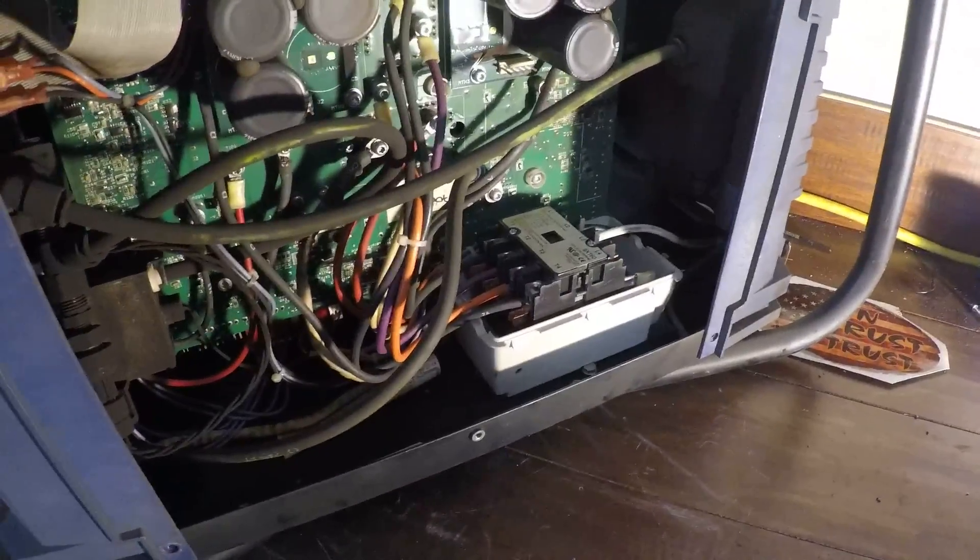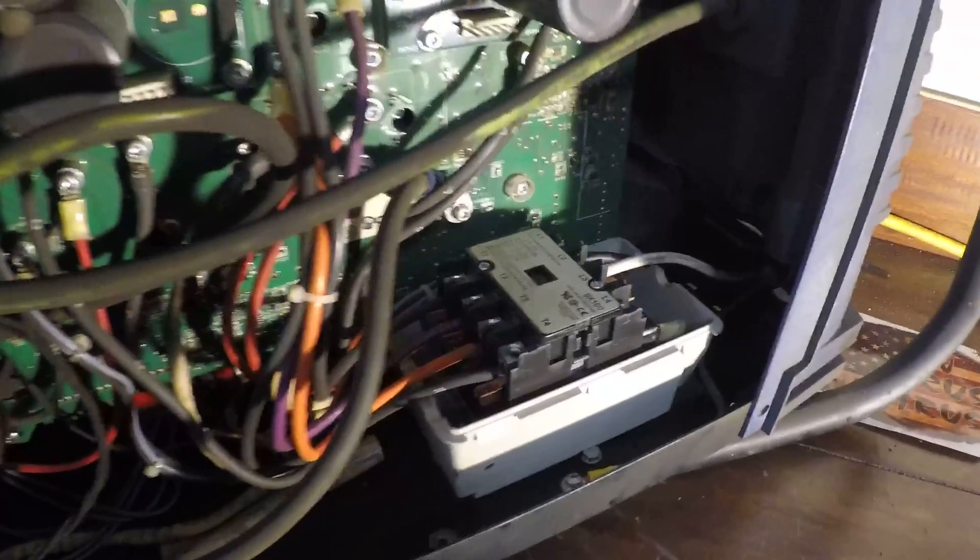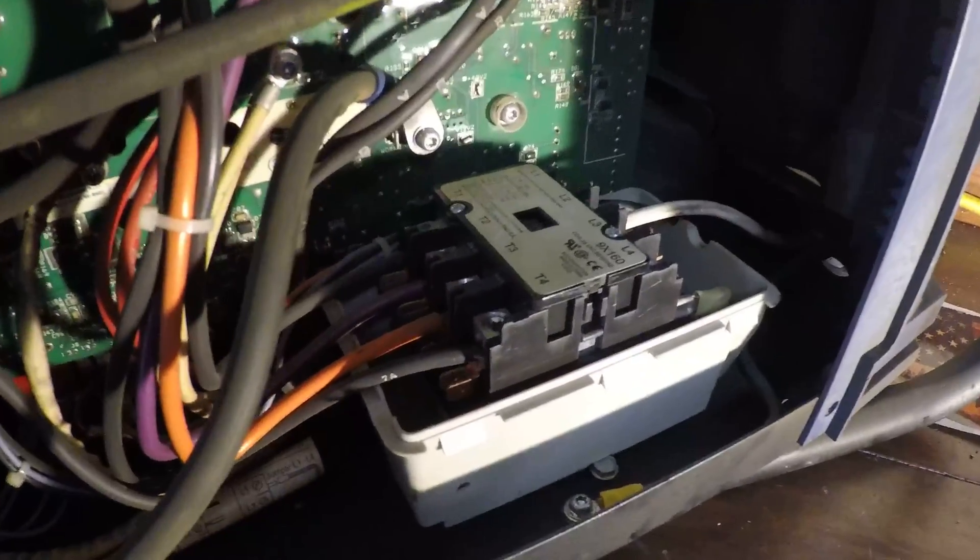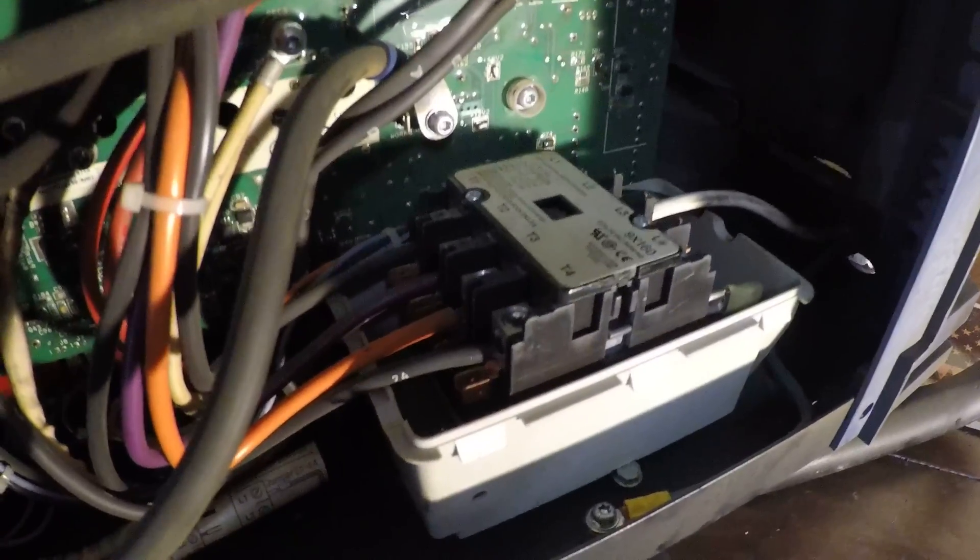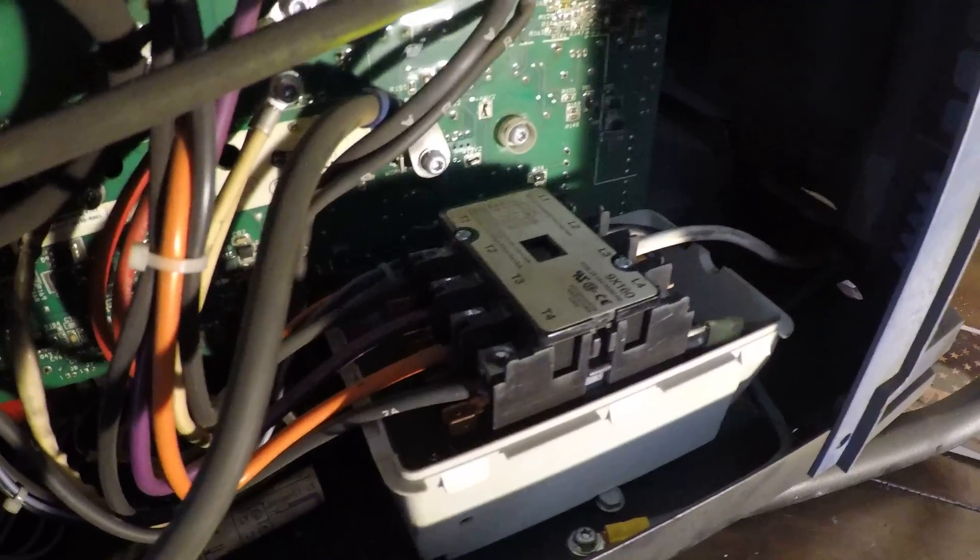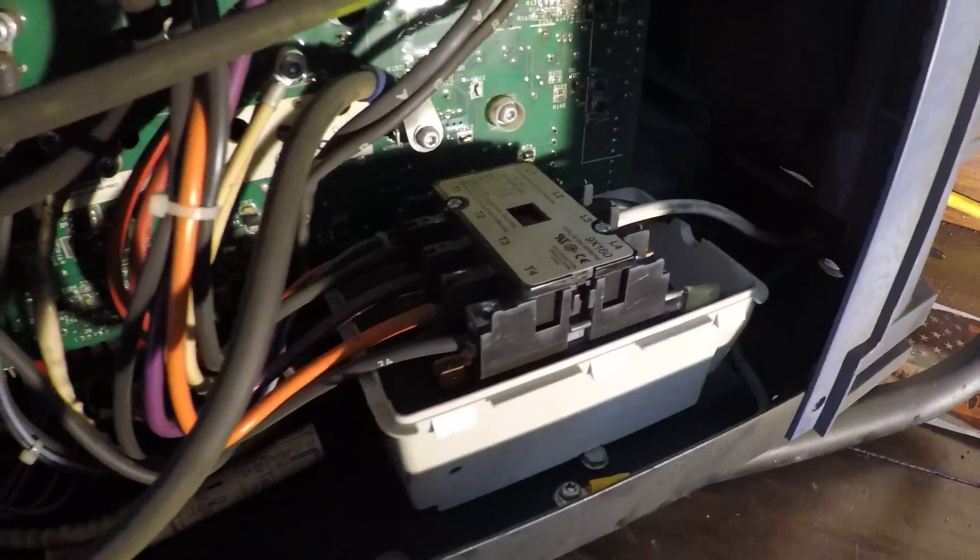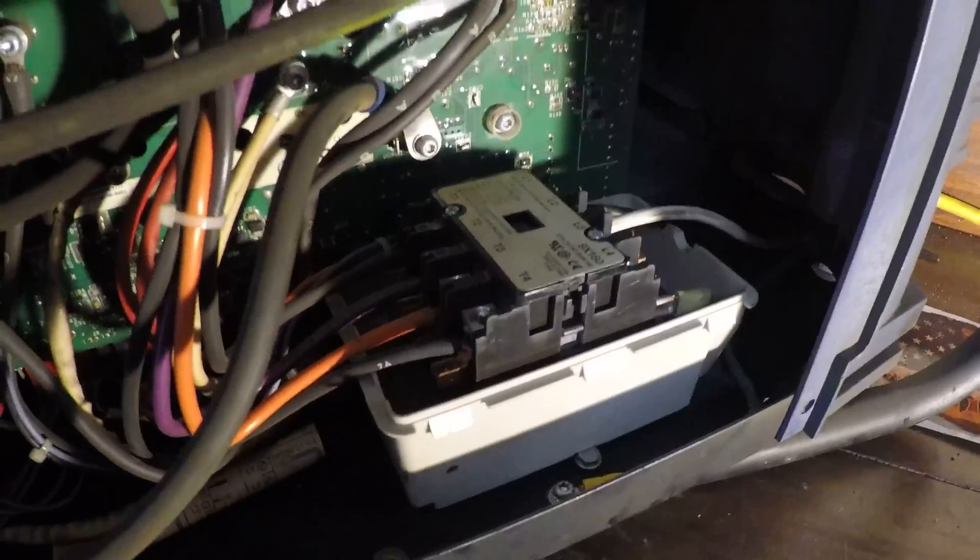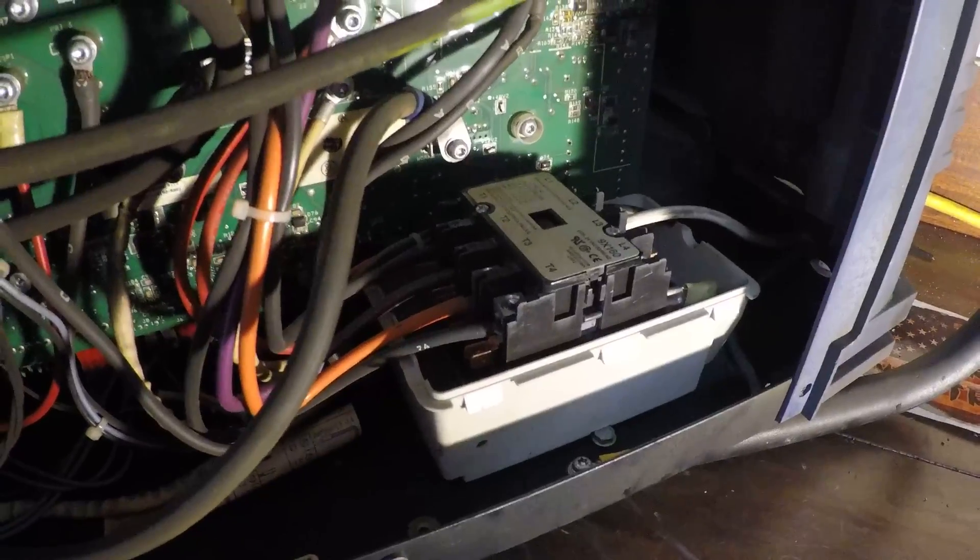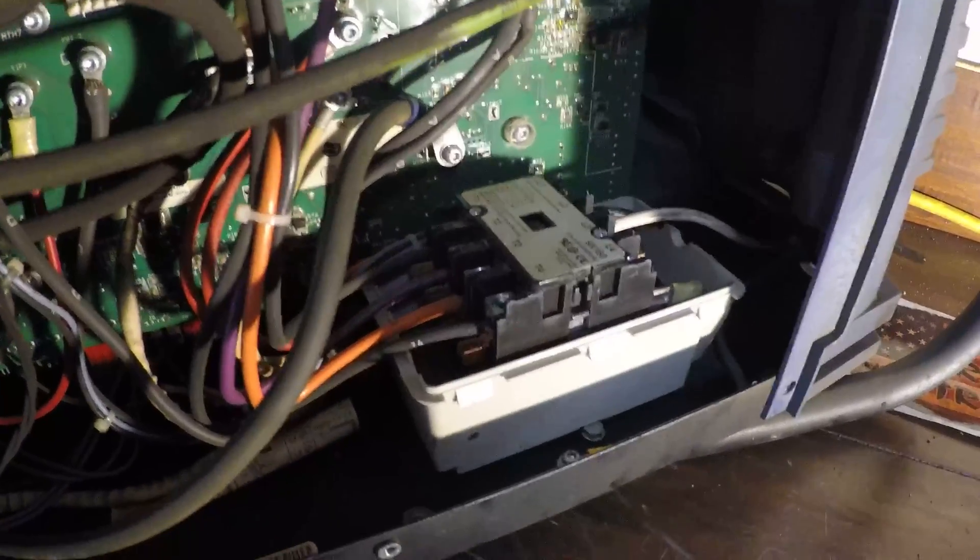The next plan of action is to order a new contactor for this thing. It's a 24 volt coil with a 50 amp maximum capacity, 220 volts. Anyways, thanks for watching.